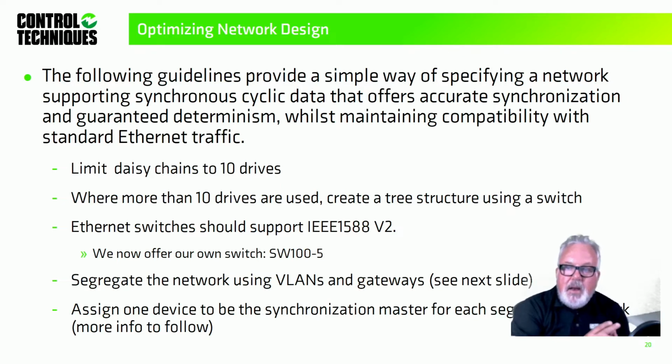So whilst maintaining compatibility with standard Ethernet traffic. If you need to have more than 10 drives in a line, you want to use a tree structure with another switch. And again, Ethernet switches should support the IEEE 1588 v2 protocol. We do sell a switch that we have private labeled. I mean, we don't make switches, but SW100-5 is the model number of that switch.